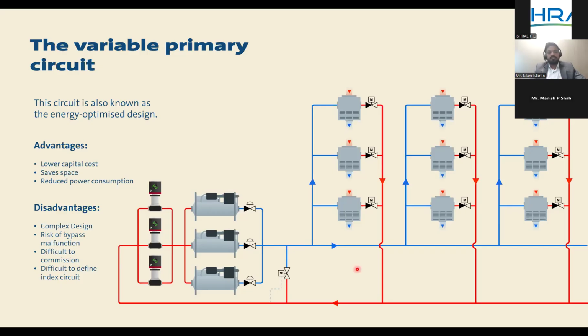So to see the advantage and disadvantage of variable primary system, it's pretty simple. Compared to variable secondary, variable primary is having a little benefit on the capex. It saves space. It reduces power consumption because your chiller and most of the equipment are varying based on the demand. So we save when we vary the speed of the equipment to meet the varying demand at the load side.